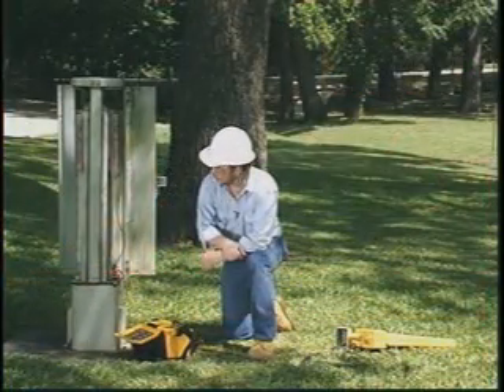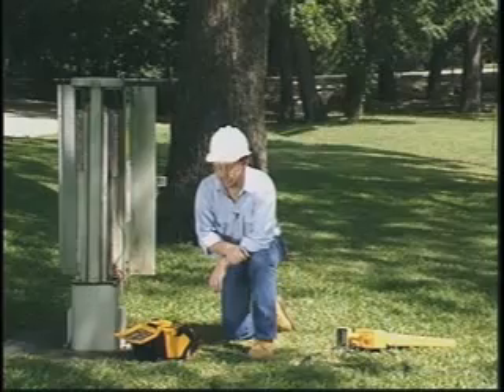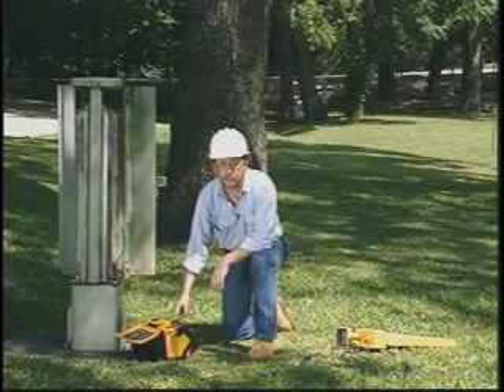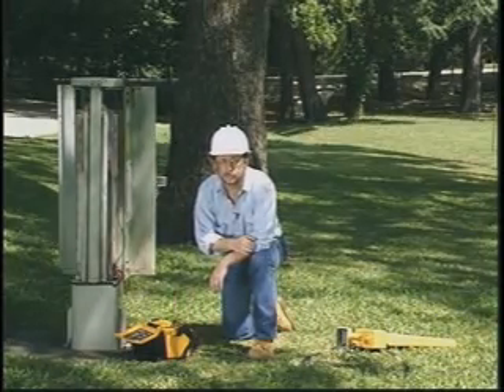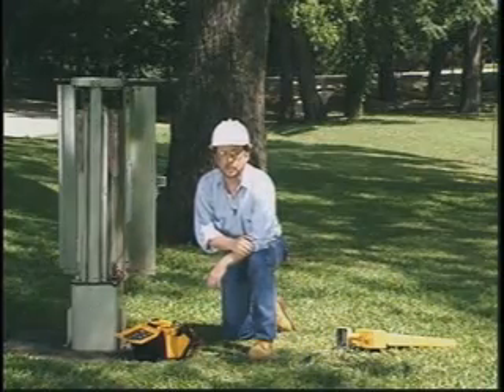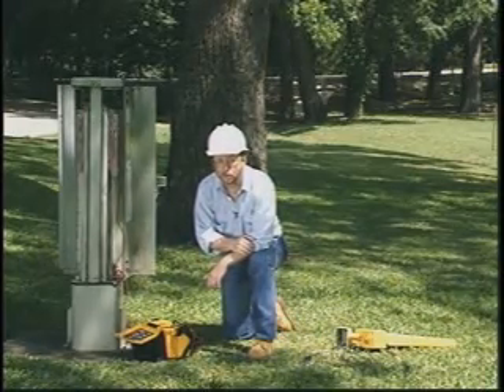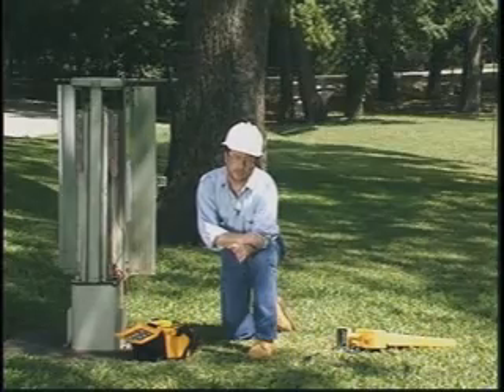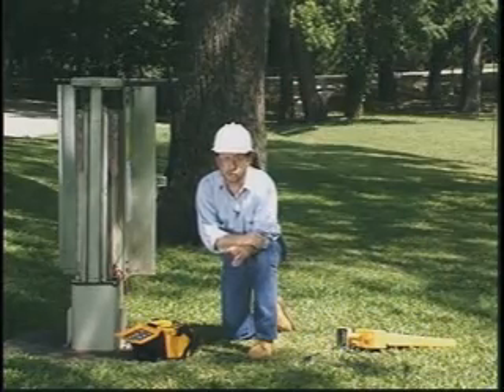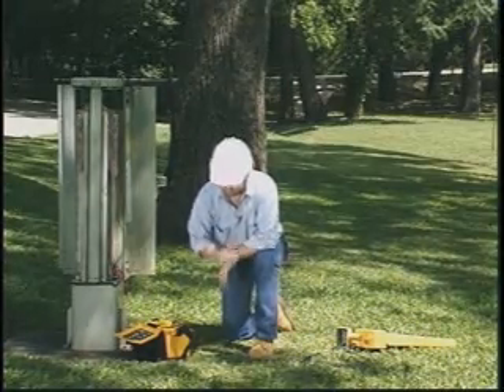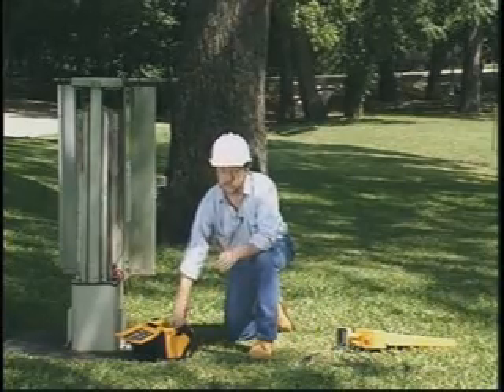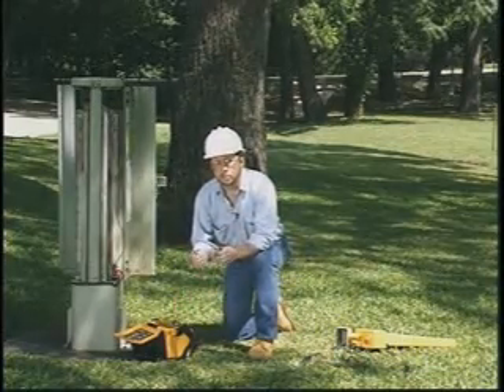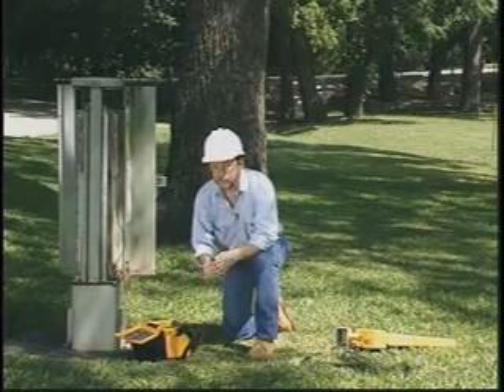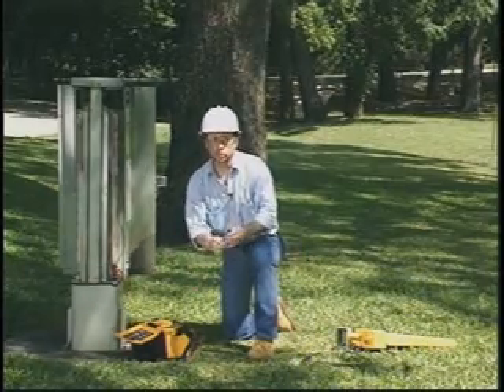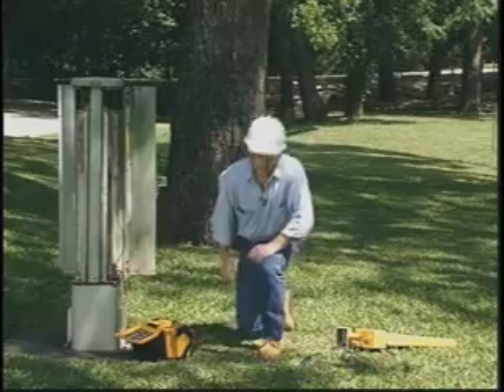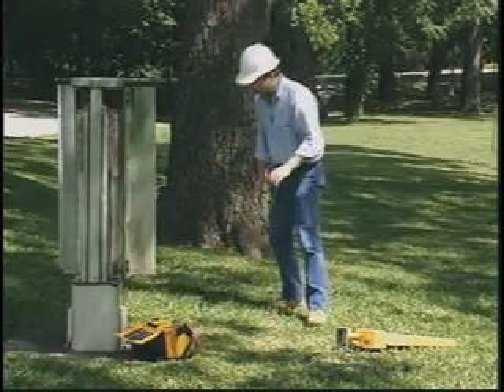I'm just about set up at this pedestal to locate a fault. The direct connect cable is plugged into the transmitter's output jack. The cable's red clip is attached to the shield of the section containing the fault. I've isolated it from ground by removing the bonding straps from both ends of the section. The black clip attaches to the ground rod, and it's placed in line with the cable path. The suspected cable path is this way, so I'll put it back here. Place the ground rod as far away as possible.